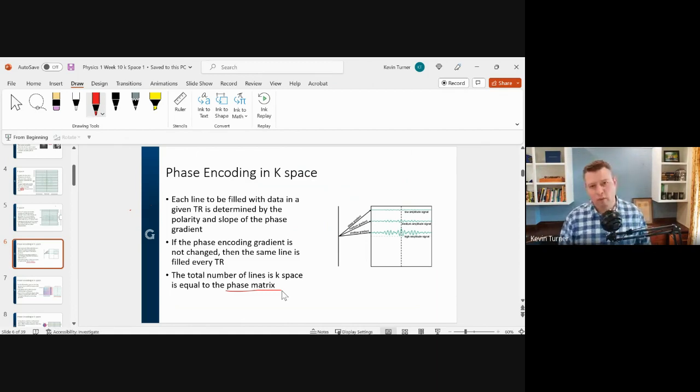Some of you may have seen this before, where you're scanning a 3 or 4 minute scan, and then the patient squeezes the ball, and you hit the stop button, and you had 10 seconds left on the scan, and then you get no images because you didn't fill up K-space. If it needs 256 and you fill it up to 255, and then you hit fast Fourier transform, the computer says no, you get nothing. Everything is trash. It must be filled up with the full amount of K-space. There are acquisitions and other things that we'll talk about later about why you sometimes see some of those images, but no image will be formed unless you fill up all the lines of K-space.